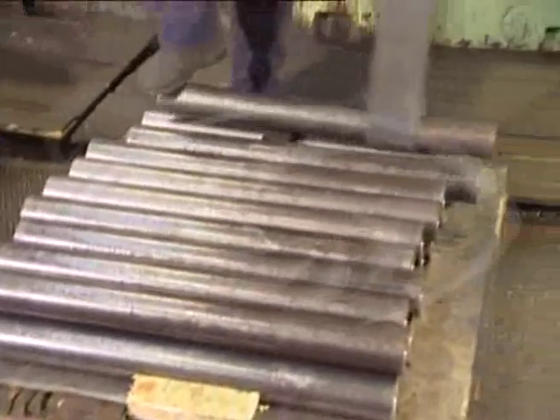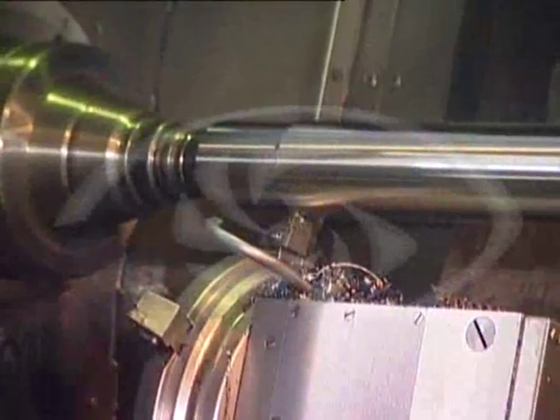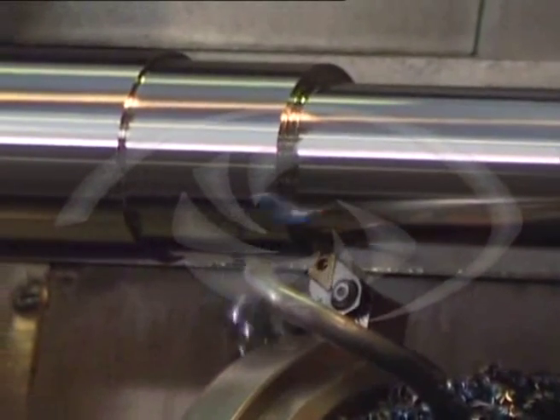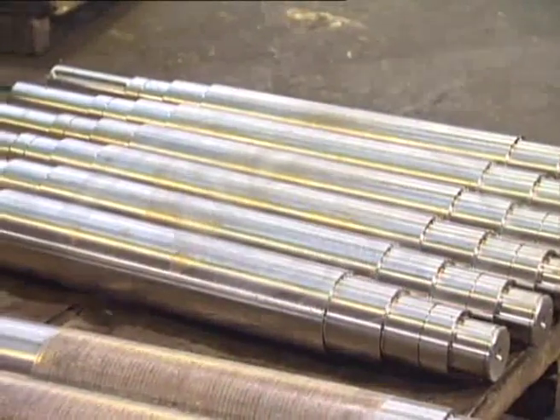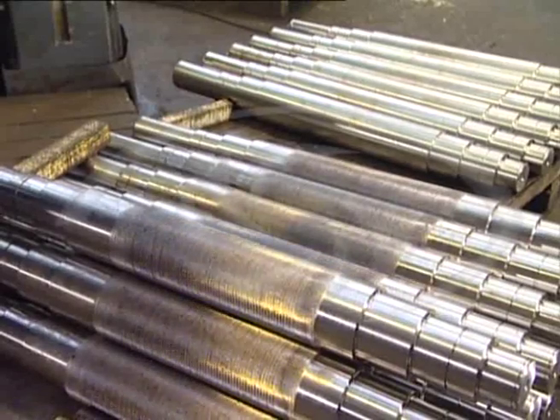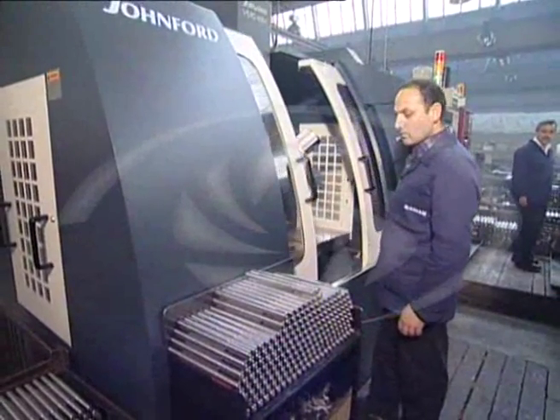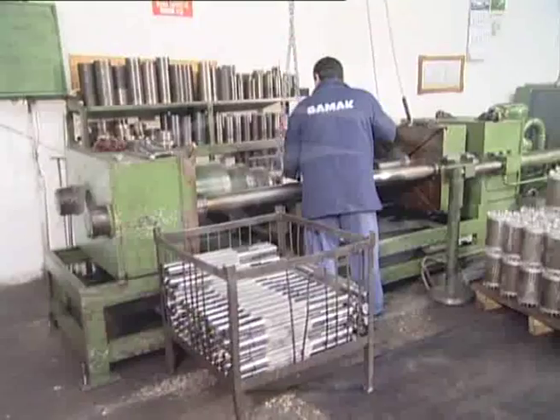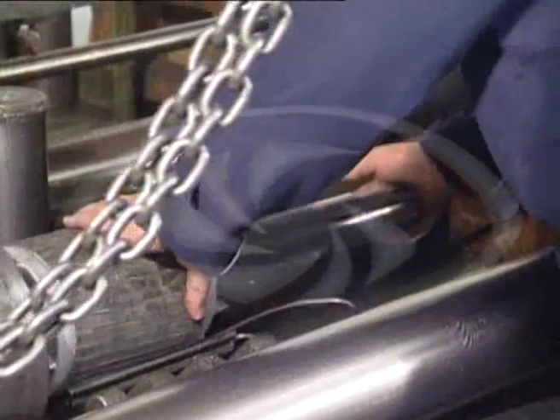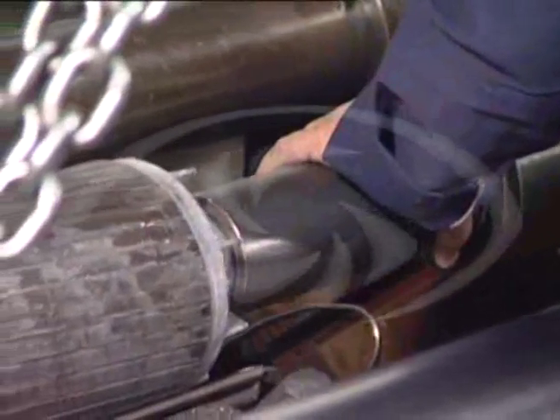After cutting the shafts from big motors, they are carried to another machine to open center holes, drill and tap from one end. Second step is precision turning of shafts. Third step is knurling the shaft in order to obtain a press fit into the rotor. Fourth step is machining keyways in shafts. Machined shafts are pressed into the rotors.